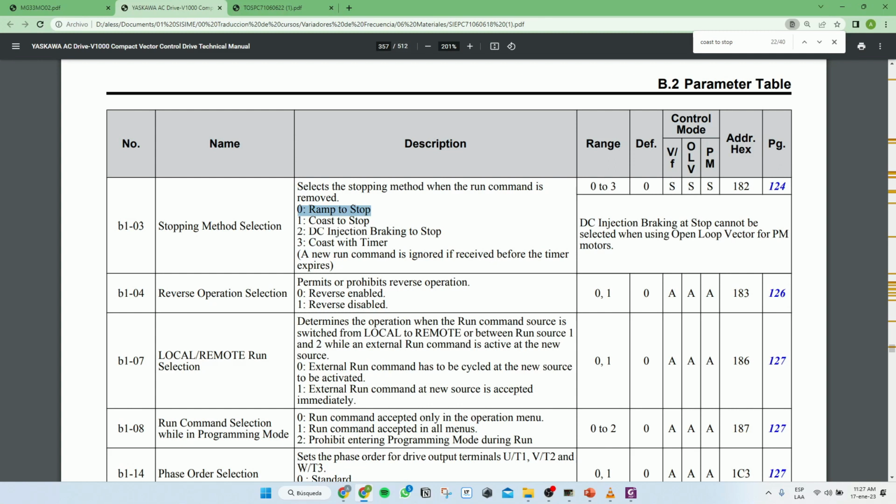Do you think that it's going to remove that voltage from one point to another? No, right? So when we press stop or a stop button, it will gradually decrease our stator voltage. And that calculation, the drive already knows how much to decrease so that it gets to the desired deceleration. So that means that it's going to be removing that voltage until it gets to 0.